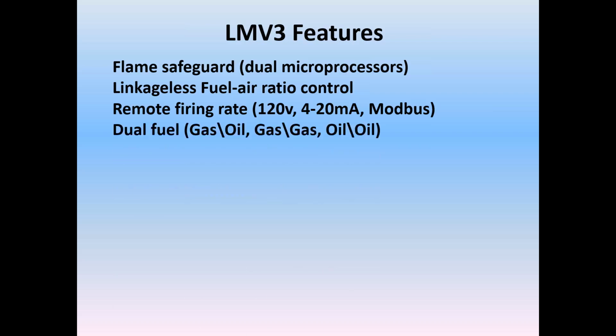It can be dual fuel. Typically, that would be gas and oil, but it can be straight gas. You can also do 2 different gases or 2 different oils, or any combination thereof. It has 2 rotary actuators, typically fuel and air, that are active. 3 of them get wired, so you would use air and gas to do a gas fire job, and then the same air actuator and oil for an oil fire job. So you wire up 3 servos, but only 2 of them are active on any fuel.